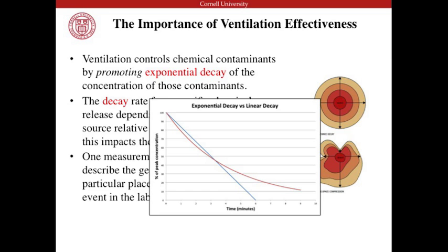So it actually ends up being an exponential decay. When we release the CO2 in the space, we bring the CO2 levels up to about 10,000 ppm - we don't want to go any higher than that because it gets dangerous. And then we watch the ventilation; we calculate this in an Excel spreadsheet after. We watch the ventilation remove the CO2 levels down, and it looks something like this.